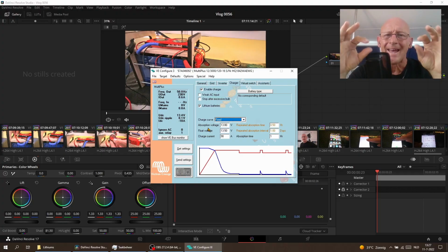That's a beautiful thing with lithium batteries - the absorption time is so short. On the Victron app on my phone, it shows a maximum of 10 minutes absorption time daily, while our lead acid batteries could sometimes be in absorption for 5 long hours, charging the last 20% of the batteries. Lead acid batteries need to be fully charged most of the time, because they don't like not being fully charged, and if you don't charge them fully on a regular basis, their lifespan goes down.